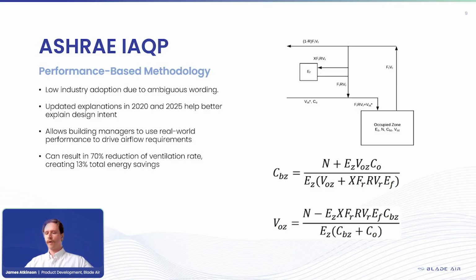Now, there was historically quite low industry adoption of the standard because it was, I'll say, ambiguous on how to implement it. There are 12 pollutants that are tracked, but it was up to building designers to determine the rates of generation and the rates of cleaning. So it was a bit nebulous to actually guarantee. It is a building standard, so you can use it as a design standard to reference the size of your equipment. Most people will still size to 62.2, but with the IAQP, you can now actually turn down your ventilation. You can change the operating mode to account for the IAQP.